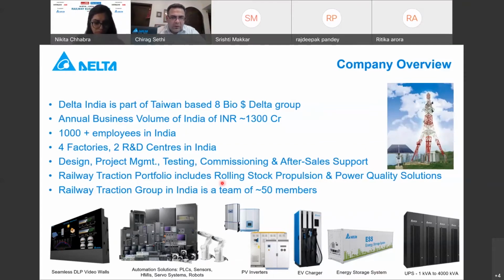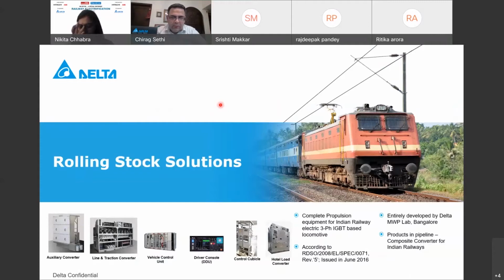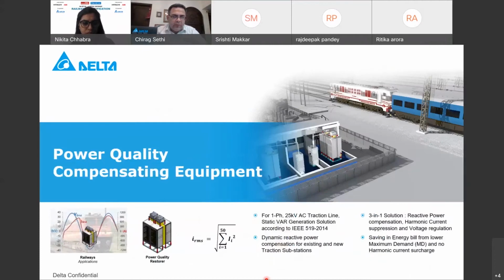Railway Traction as a group is focusing on products which are solutions specific only to railways, which consists of rolling stock propulsion as well as power quality. Rolling stock solutions is for electric locomotives, which consists of the main power converters, auxiliary converter, hotel load converter, as well as some switchboard cabinets. Power quality equipment consists of dynamic reactive power compensation for traction substations to address the issues of poor power factor, high harmonics, as well as voltage regulation. So this is a product which complies with the latest IEEE 519 standards. This is what will be the topic of our presentation today.